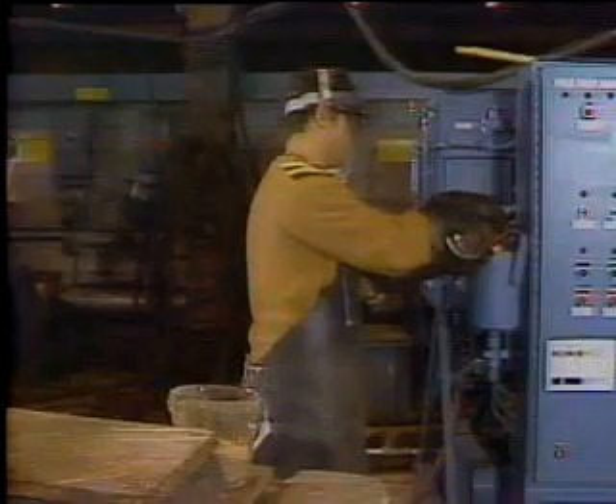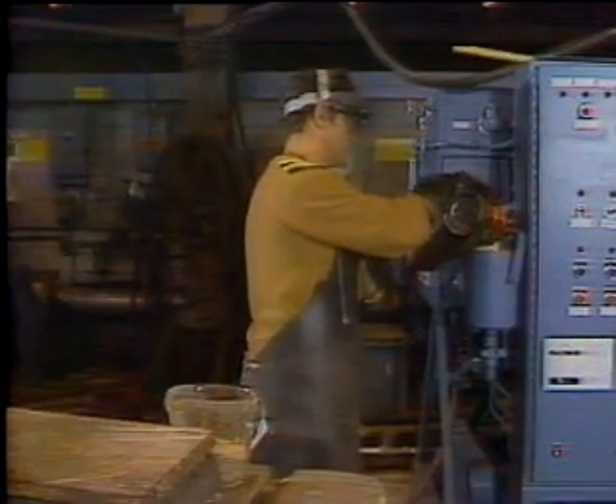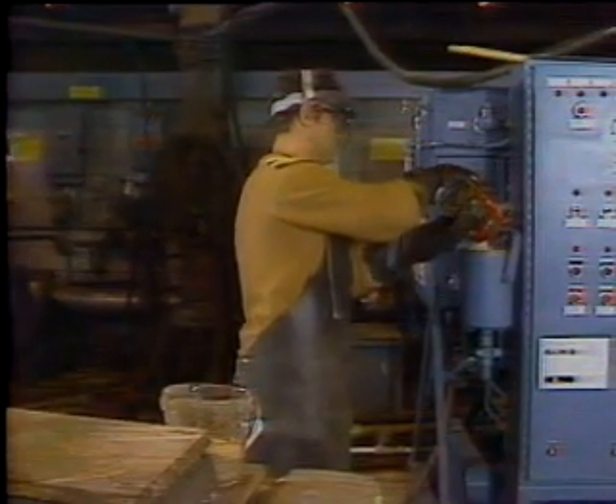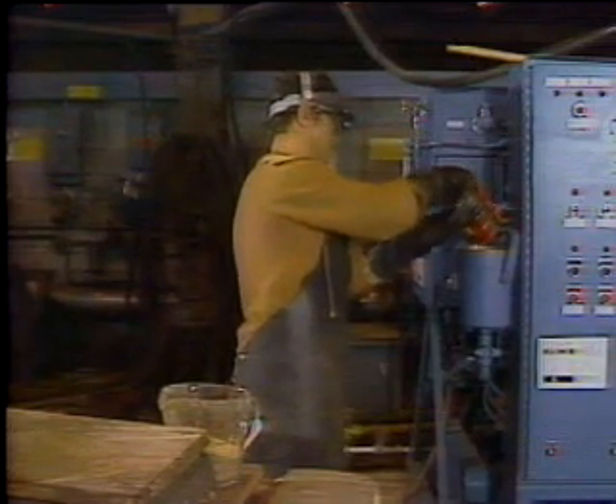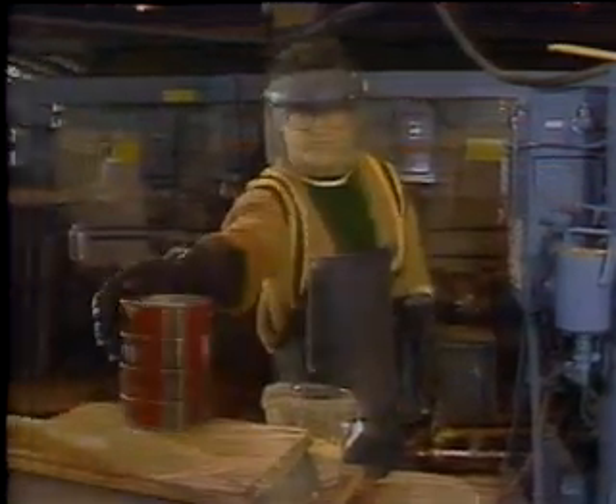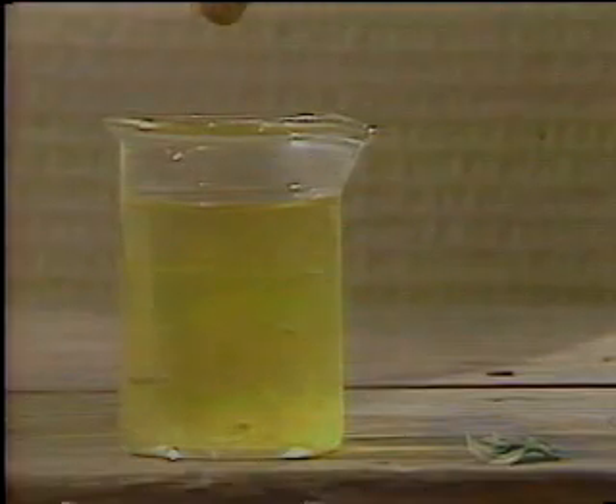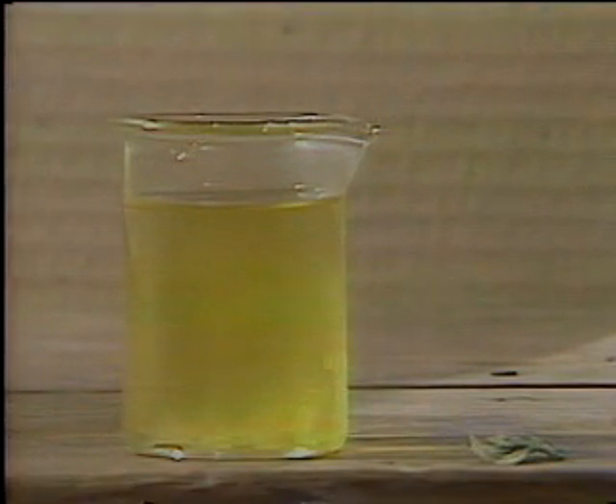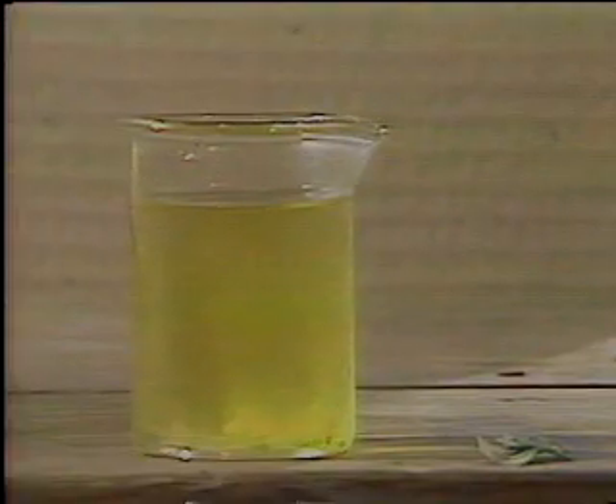It's introduced into the unit through the acid pot, just like AC2 is, but it has to be circulated at 220 degrees Fahrenheit in order to dissolve the scale properly. Be sure to read the instructions fully before you use it. It'd be a good idea to take some of the scale from the blowdown strainer and put it to the same test every now and then. If it dissolves in the concentrated AC2 solution, you probably don't have a sulfate problem. You should do this prior to acid cleaning and keep good daily logs. Your logs still need some help, so let's go over how to take these readings and what they mean so you'll be able to troubleshoot.